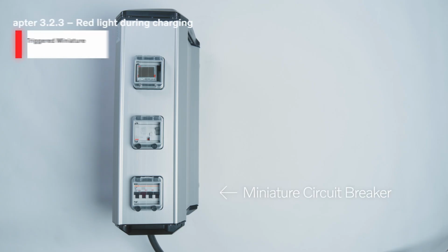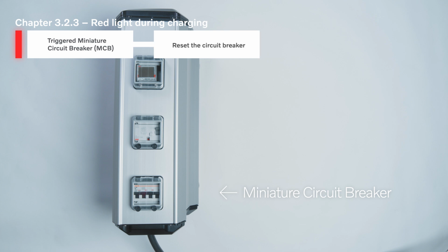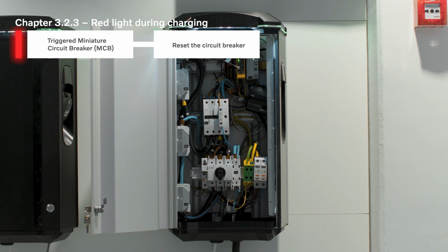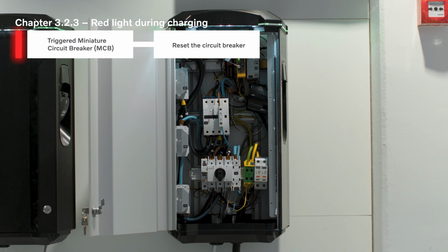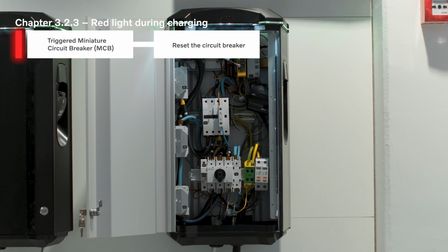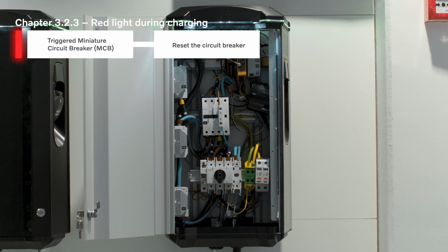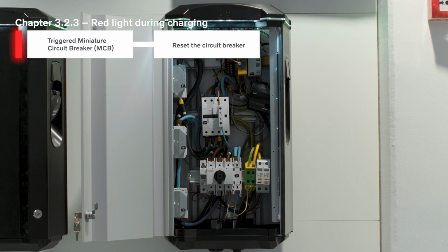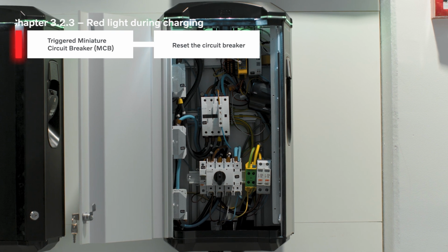If the miniature circuit breaker, the MCB, has been triggered due to overload or short circuit, you should identify the cause and reset it. Check internal wiring and components for possible reasons for short circuit, and make sure the allowed maximum current in the back-end charger configuration hasn't been exceeded.